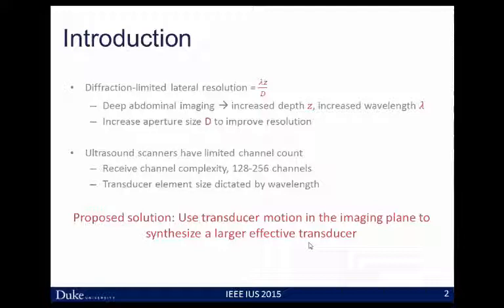One thing we can do to improve this is to increase the aperture size d. By doing that, we reduce that ratio and improve resolution, but at a cost. We can either add more receive channels, which increases the complexity of the back-end electronics and the cost of the scanner, making this not really a clinically viable solution. Or we can increase the individual element size on our aperture, but in doing that we introduce grating lobes as we begin to steer our beam.